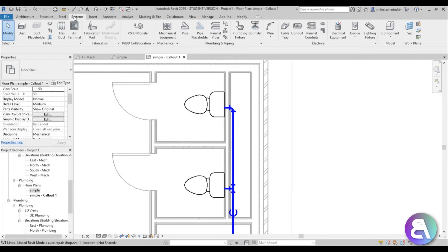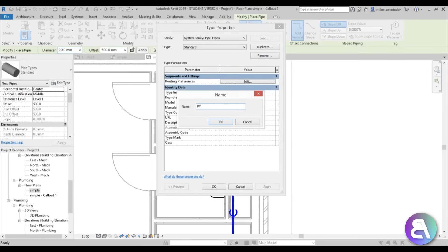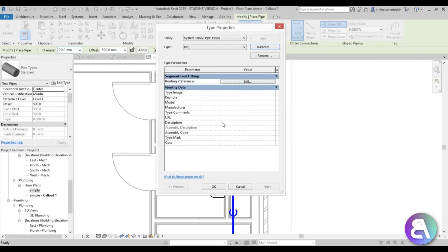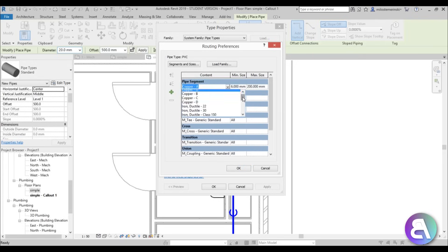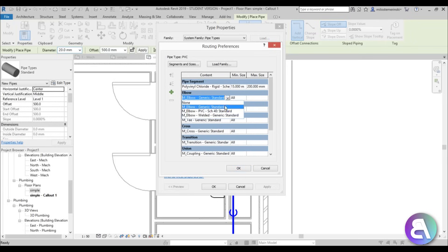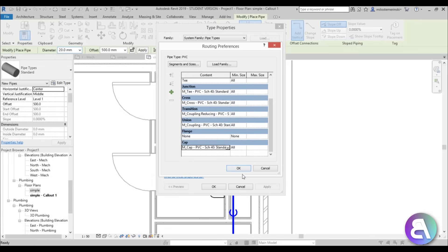Go back to the Systems tab, select Pipe, and click Edit Type. Duplicate the Standard type and call it 'PVC.' Then go to Routing Preferences > Edit and change all the routing preferences to the new PVC elements — select Polyvinyl Chloride Rigid Schedule 40 for each category. For the preferred junction type leave it at T-junction; for the cap use PVC Schedule 40. Leave flange set to None, then click OK.